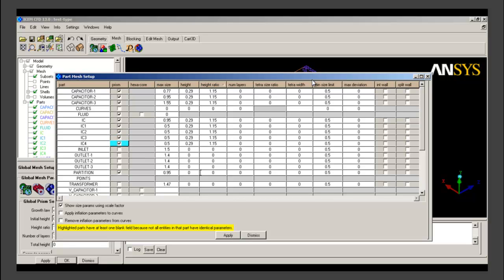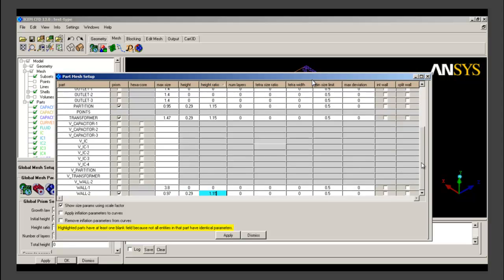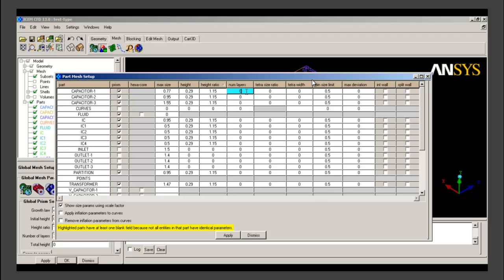For the partition component we activate the prism layer, give first cell height as 0.29 and height ratio as 1.15. Even for the transformer component we give prism layers — around all solid components we need to capture near-wall flow, so we grow prism layers near all of them. For wall 2 also we give first cell height as 0.29 and growth ratio as 1.15. In addition to first cell height and growth ratio, we give the number of layers as 3. For turbulent flow around solid walls, 3 to 5 prism layers are mostly sufficient, so we give 3 prism layers for all components.